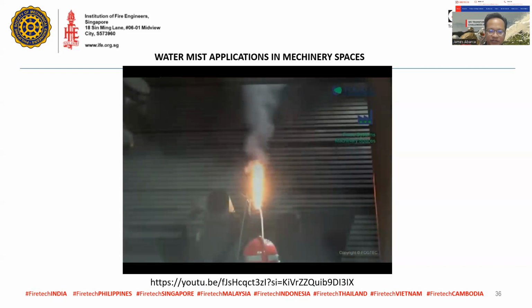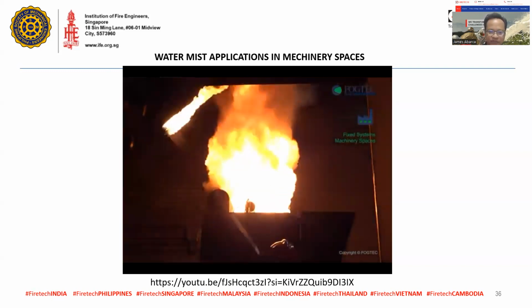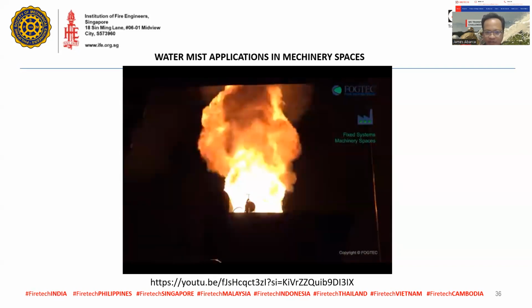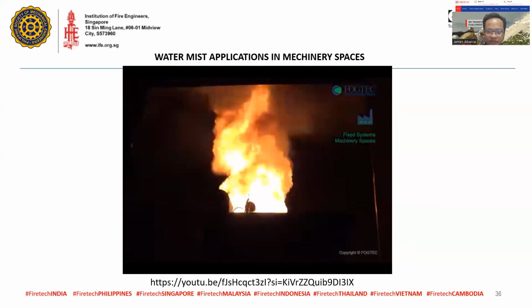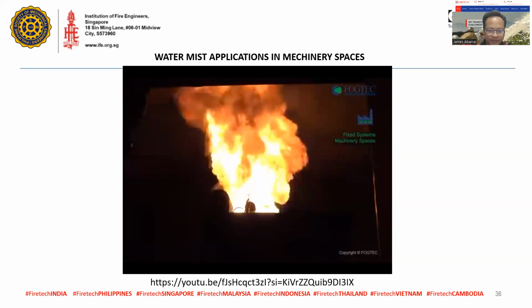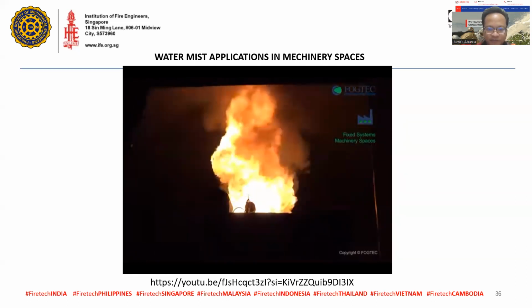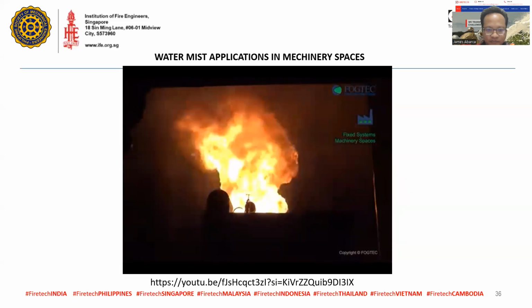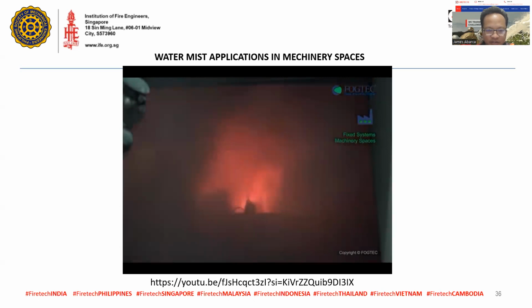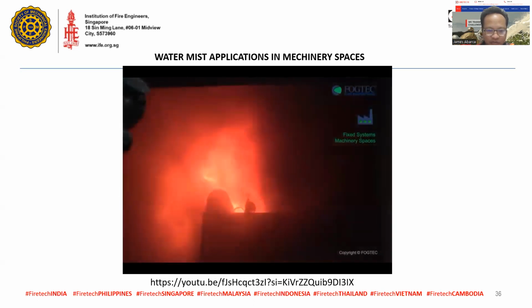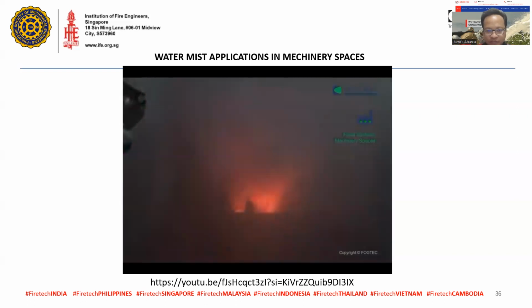Okay. Next, we try to simulate on some fuel hazard as well. Okay. These are class B fire. So there you go. Mist will be introduced once again. See that? Always it goes with a high pressure and try to envelop the fire. That's how the application is for a water mist system. So before that mist even will reach below or protected area, it already evaporated because of the tiny particle, and it will cool the environment.